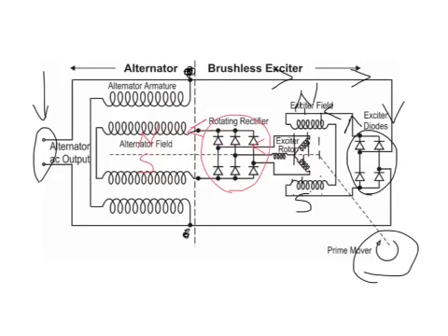So now we have these magnetic lines of force that are turning at rated speed, cutting across our alternator armature conductors. Now the alternator armature conductors have a voltage induced in them because we have relative motion between a magnetic field and a conductor. So we now produce a voltage at our alternator output.